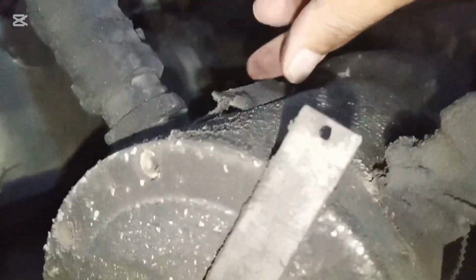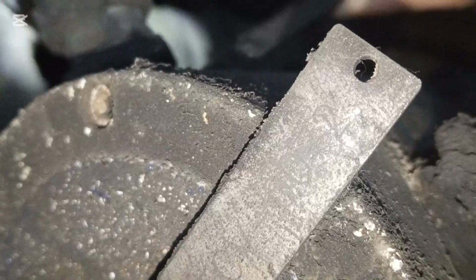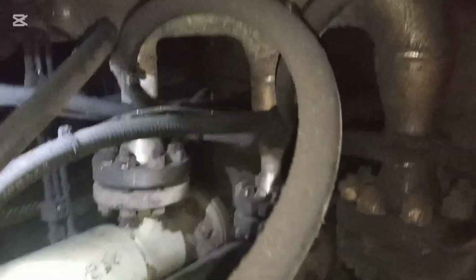We also opened the gas turbine inside, and here are 3 valves. These are motorized valves, and to the valves there are 3 air connections. The inspection had not been done for many days, so there are some dirty particles inside the panel of the motorized valve, MOV. We also opened its air connection line and checked whether the line is blocked or clear, and we saw that the line is clear. Here is the connection from a common connection; the air line comes to different lines to the valves.